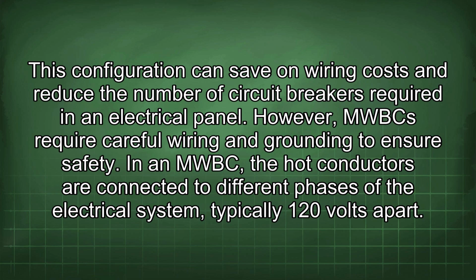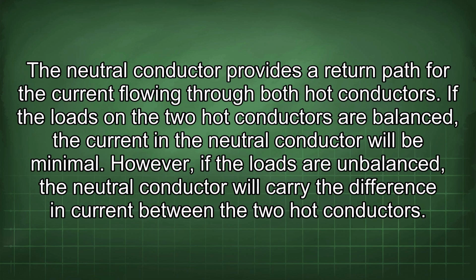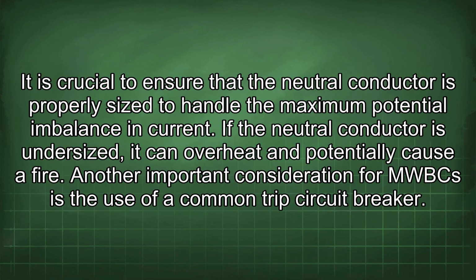In an MWBC, the hot conductors are connected to different phases of the electrical system, typically 120 volts apart. The neutral conductor provides a return path for the current flowing through both hot conductors. If the loads on the two hot conductors are balanced, the current in the neutral conductor will be minimal. However, if the loads are unbalanced, the neutral conductor will carry the difference in current between the two hot conductors. It is crucial to ensure that the neutral conductor is properly sized to handle the maximum potential imbalance in current. If the neutral conductor is undersized, it can overheat and potentially cause a fire.